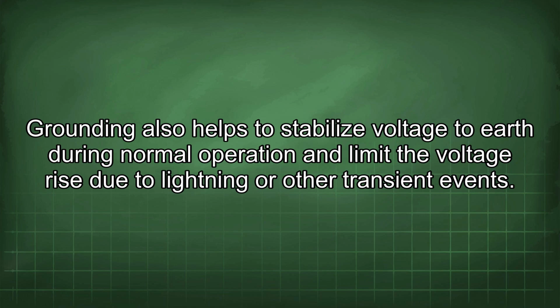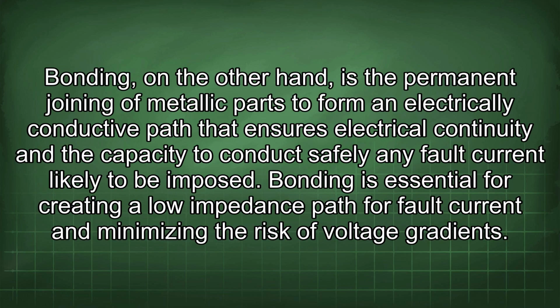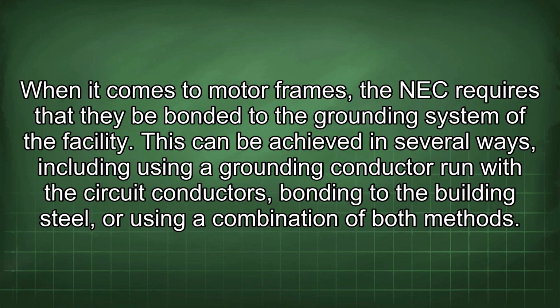other transient events. Bonding, on the other hand, is the permanent joining of metallic parts to form an electrically conductive path that ensures electrical continuity and the capacity to conduct safely any fault current likely to be imposed. Bonding is essential for creating a lower impedance path for fault current and minimizing the risk of voltage gradients. When it comes to motor frames, the NEC requires that they be bonded to the grounding system of the facility. This can be achieved in several ways, including using a grounding conductor run with the circuit conductors, bonding to the building steel, or using a combination of both methods.